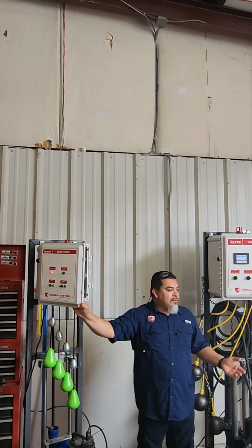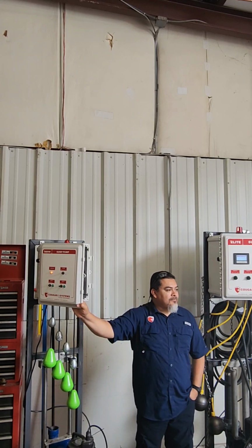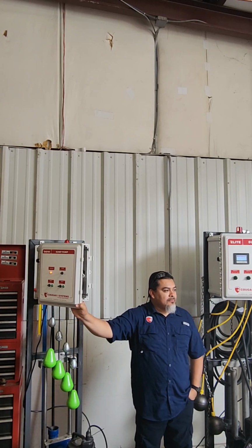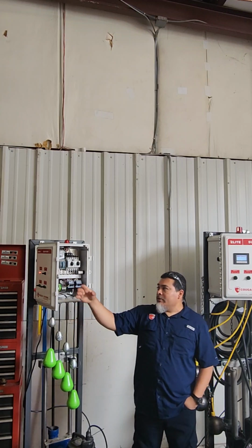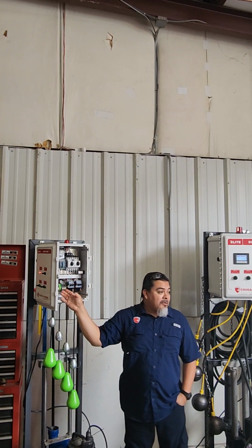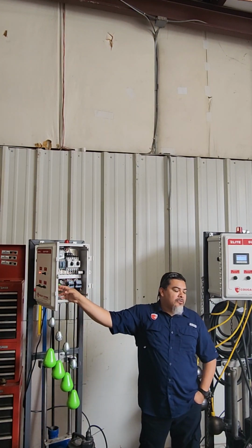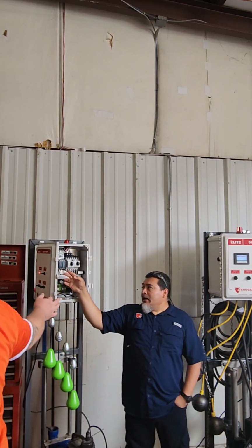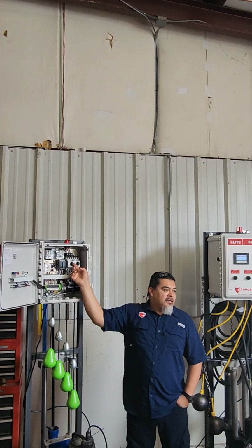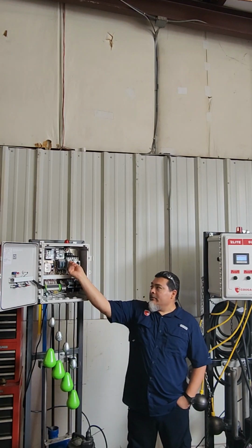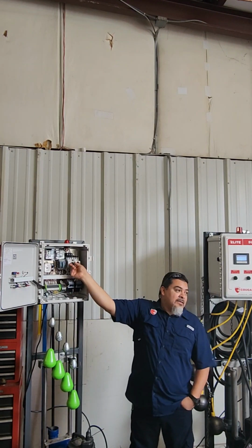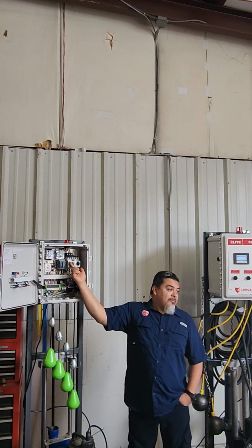What's a good sequence to run through? As like you get there, what's a good sequence to run through to check out everything? The main sequence, of course, you want to come in, check your incoming power, which would be either 480 or 230, three-phase, single phase. After that, verify whether these are tripped. Are they vertical with an angle or sideways? Trip is always at an angle.